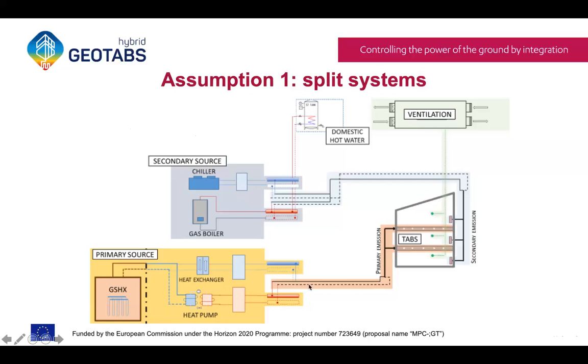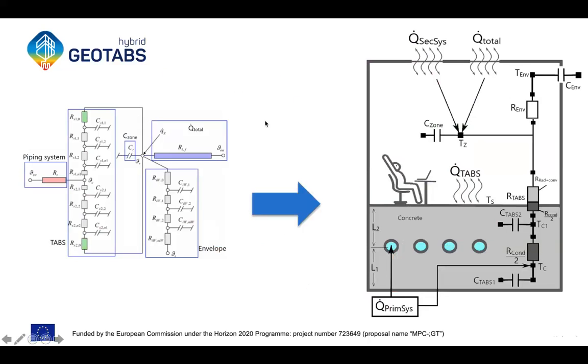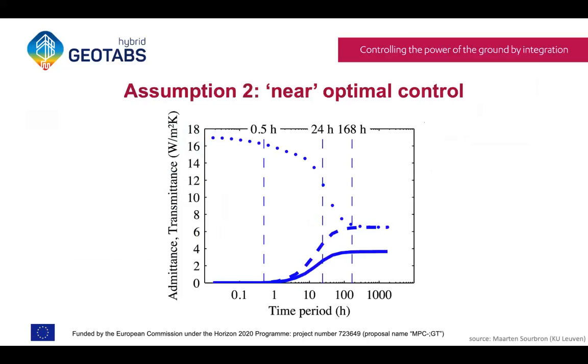Because we can assume this split, we can simplify the actual simulation of the system into a reduced order scheme, as we see here, where the total heating and cooling demand is split between a part for the secondary system that is instantaneous, interacting directly with the zone temperature, and a part for the primary system, the GEOTABS system, that interacts with the zone with intermediate latency due to the concrete. This is very important because the excitations of the concrete will be attenuated by its thermal mass.